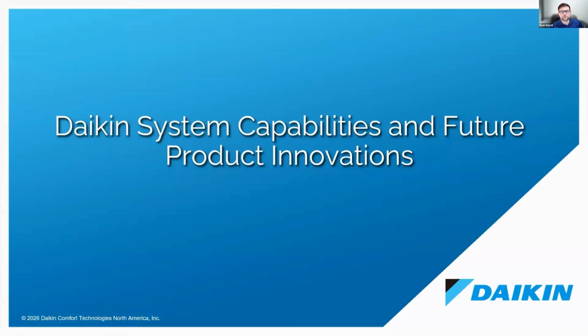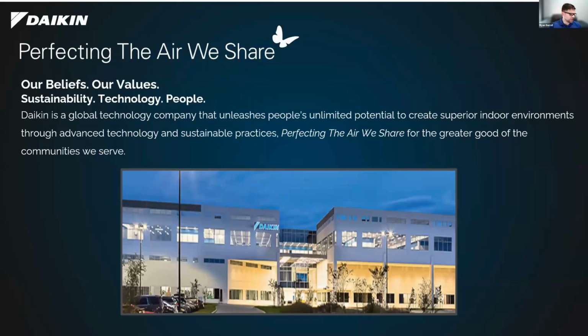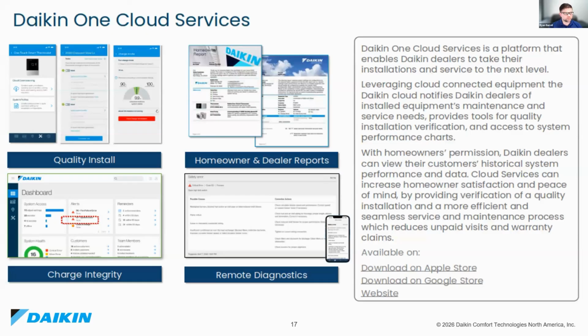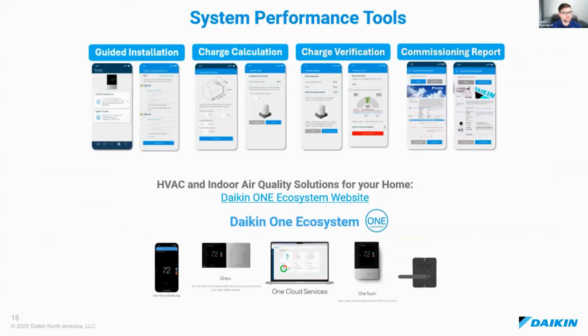performing correctly. All right, so what's Daikin doing about all this, and how are we trying to change the game, at least for new equipment installations? Our Daikin One cloud services is currently available for contractors. We can provide quality installation verification reports with the majority of our inverter heat pumps and AC furnaces, our Daikin Fit line, as long as they're using our Daikin One cloud services platform and controllers. We actually have the ability to provide commissioning reports, actually measuring and verifying how the installation is going. So: guided installation, charge calculation reports, charge verification reports, and actual commissioning, telling us what capacity, how many BTUs, whatever you sold or promised to deliver that customer, you can actually stand behind.